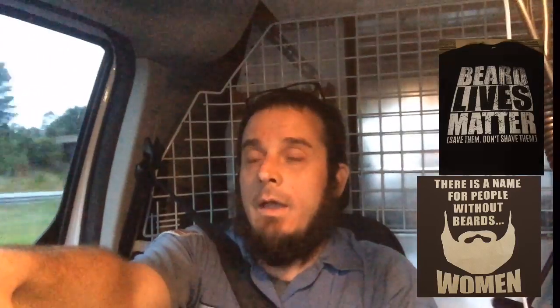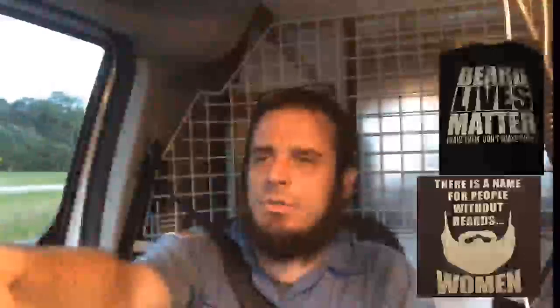I had a little situation I wanted to talk about. The unit I checked out on the Dirty Maintenance North Carolina video was tensors, and everything had gone back to working normally. But I got back out there today and the unit was pumping down again — ridiculously high head pressure with no subcooling, at least not during the few seconds the system tried to run, and 105 degrees of superheat.